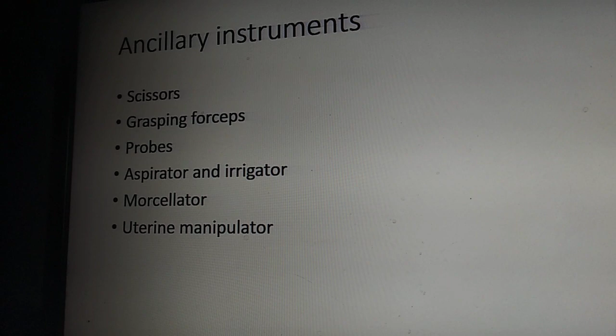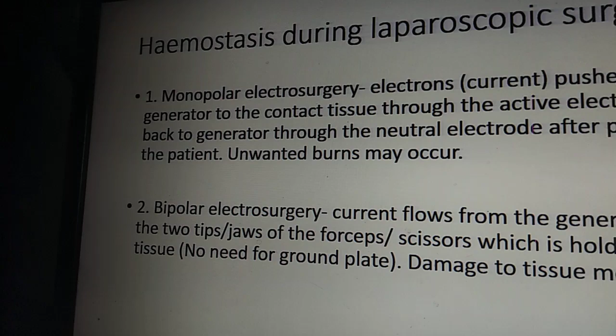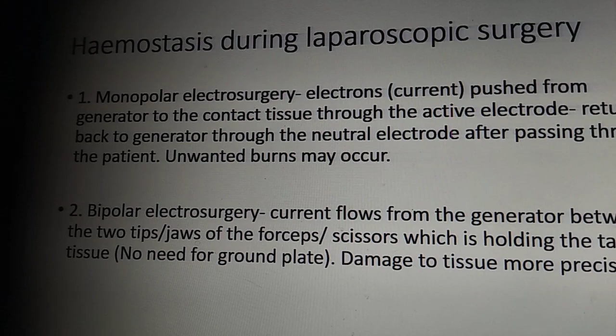Now coming to hemostasis during laparoscopic surgery. As you know, like even in laparotomy, we have monopolar electrosurgery and bipolar electrosurgery. Monopolar electrosurgery is where the electrons are pushed from the generator to the contact tissue through the active electrode and then returns back to the generator through the neutral electrode after passing through the patient. So the problem is unwanted burns may occur. That is a scary thing about monopolar electrosurgery.